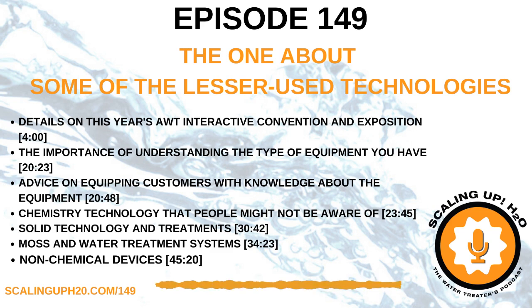We had just installed a controller at a convention center, and Friday afternoon about 4 o'clock, we received an alarm. We received a second alarm, and what happened was the makeup solenoid valve stuck open. When you're dumping 150 to 200 gallons a minute overflow in the tower, and everyone goes home at 4 o'clock, that system would have overflowed all weekend until Monday. We were able to contact them, they were able to bring somebody in, made the repair, and I think it saved them $6,000 to $7,000 just that one time.